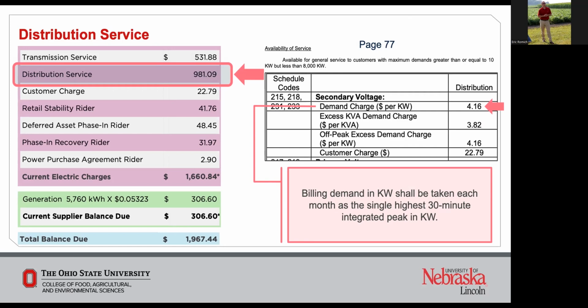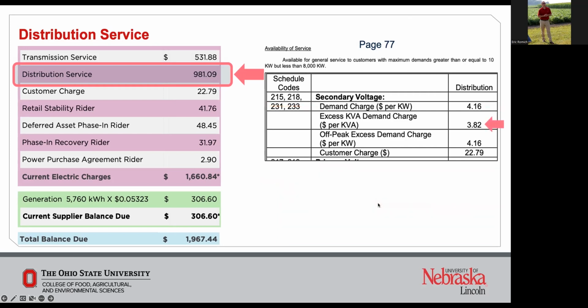And so in Ohio, a lot of ours are based on 15-minute demand windows, and within those demand windows are 5-minute intervals. So if you can imagine this 15-minute window rolling through all these 5-minute intervals, the highest 15-minute demand spike over the billing period is what they would classify as setting that demand. So it's important to read how they're calculating these demands, because different utilities have different rules in terms of how they're calculating them.